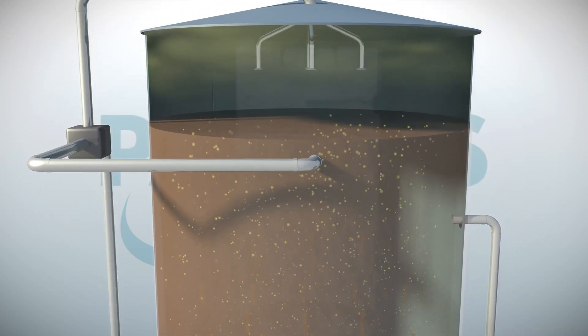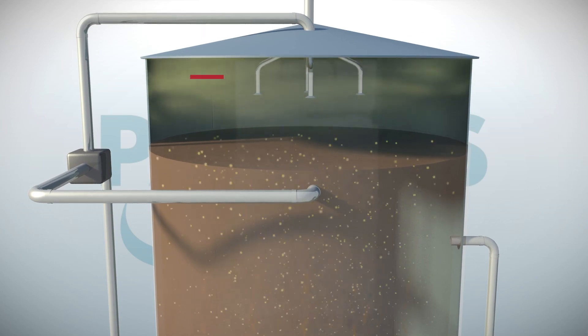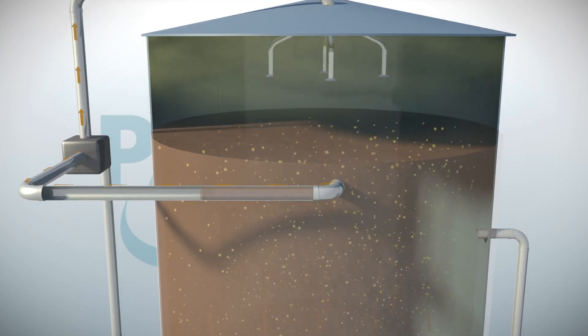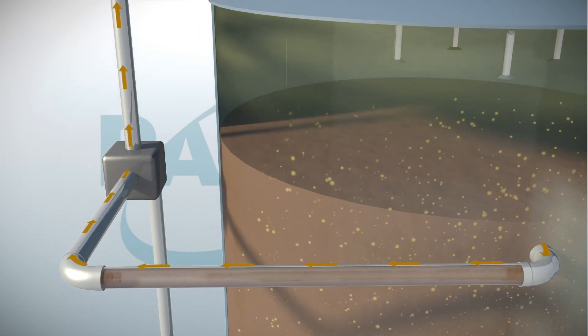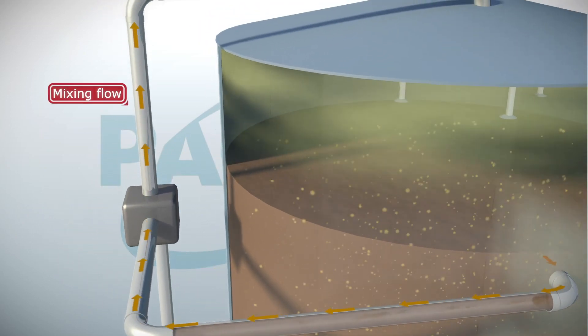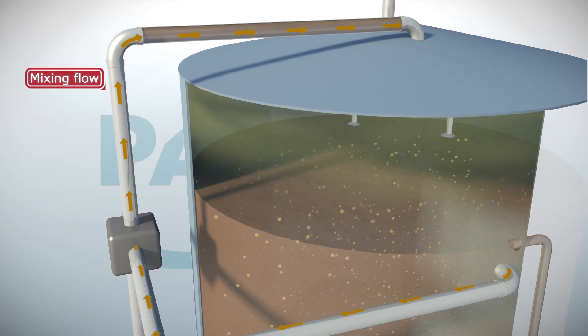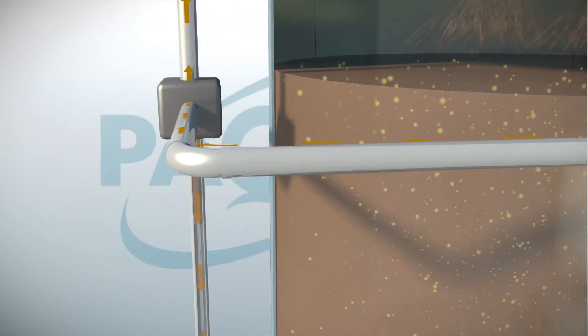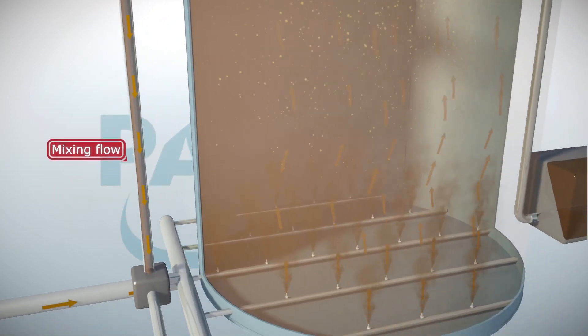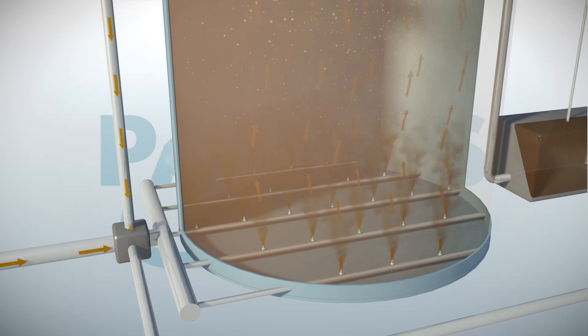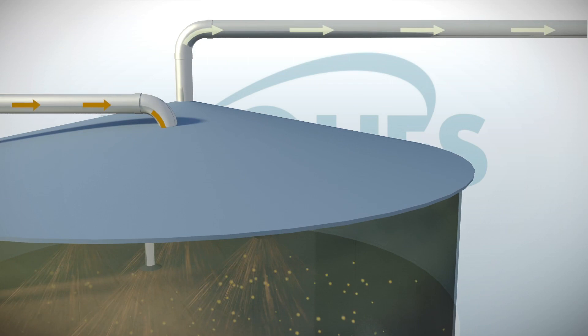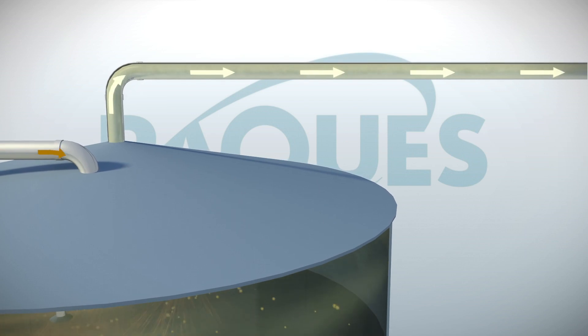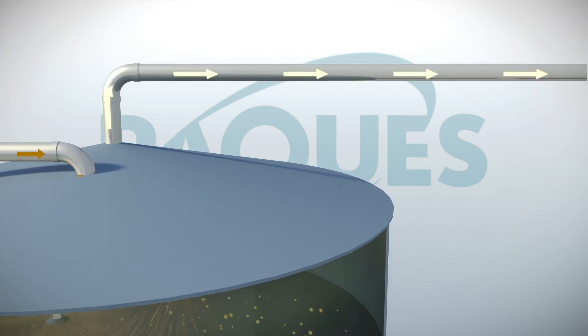The microorganisms in the flocks produce biogas throughout the whole reactor. The biogas is collected in the headspace of the reactor. Mixing in the bottom and top parts of the liquid is highest, due to the recirculation of liquid from the upper part of the reactor down to the bottom. The energy-rich biogas is collected in the headspace, leaves the bioreactor and can be used, for example, in a CHP, boiler, or can be upgraded into natural gas.